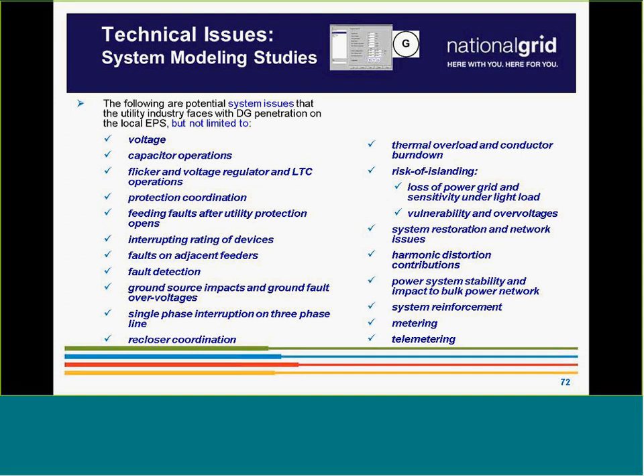I want to make sure that all of my protections still work and that the protections at your site are going to actually trip for faults on the EPS. So, in general, we look at fault detection and the impacts that your system will have on the currents coming into our system for each type of fault, and then we look at risk of islanding.